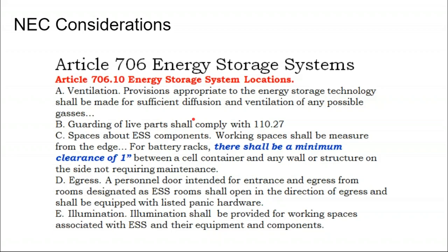Whether or not that's a good thing for your site really depends on your job site, if it's in an urban environment or if you're trying to tinker in a rural environment. Battery racks shall have a 1-inch clearance between the cell container and the wall - that's just a good practice, even for lower voltage batteries as well. The door should open outward from the battery room.